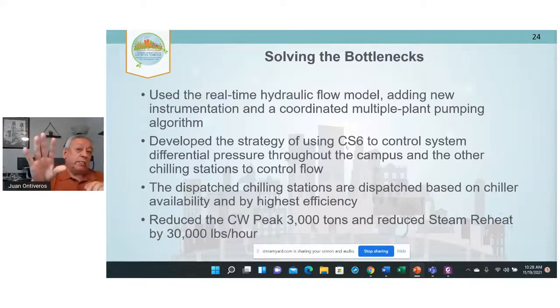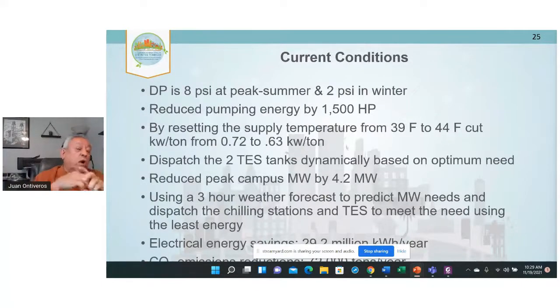By doing this, we learned that we reduced our peak cooling by 3,000 tons. And I don't have to do the reheat, using steam to reheat because it got too cold. I actually reduced our steam by 30,000 pounds an hour. So we saw that immediately. What we're doing now is this is what our current conditions are. Our differential pressure between supply and return is 8 psi in the peak of summer, and it's 2 psi in the winter. I don't need as much chill water.